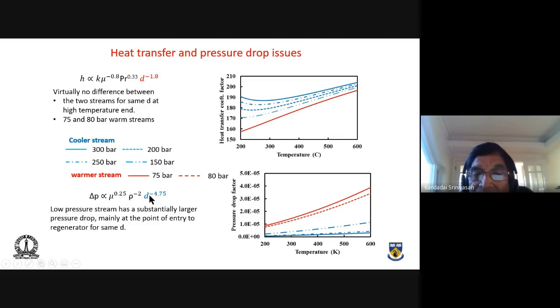These diameters have different powers - viscosity to the power 0.25 versus viscosity to the power 0.8. So pressure drop and heat transfer are correlated, and this must be kept in mind when designing heat exchangers.